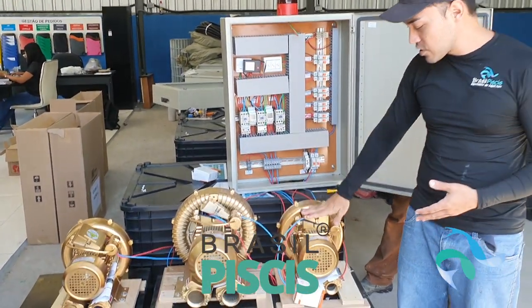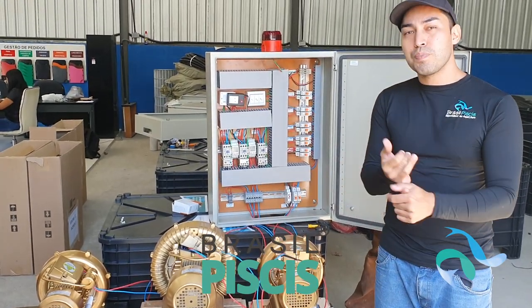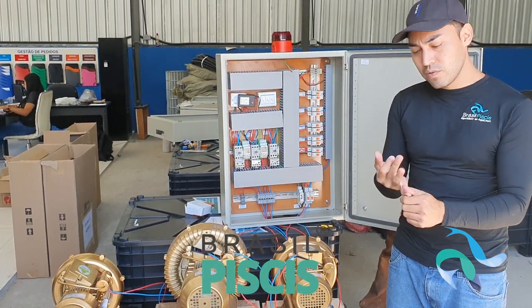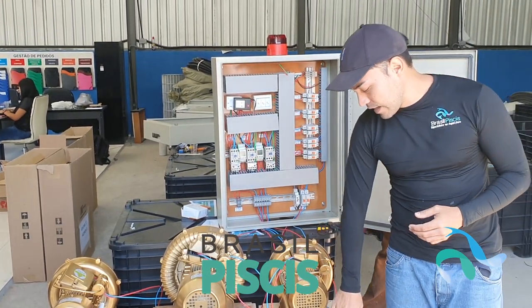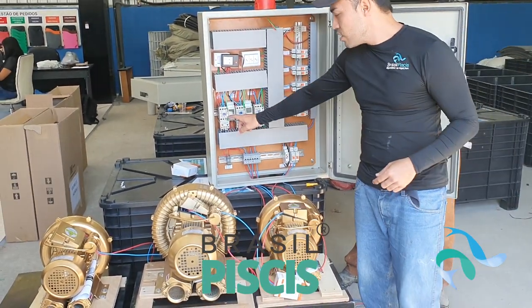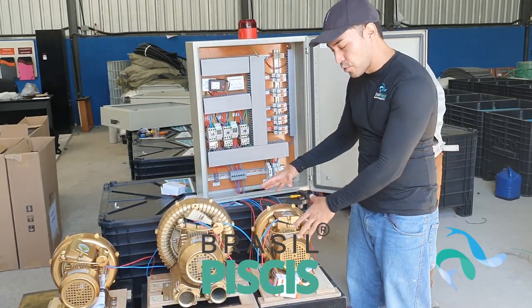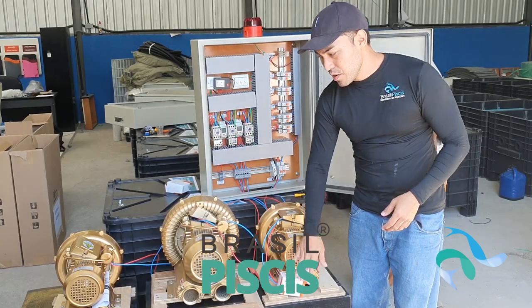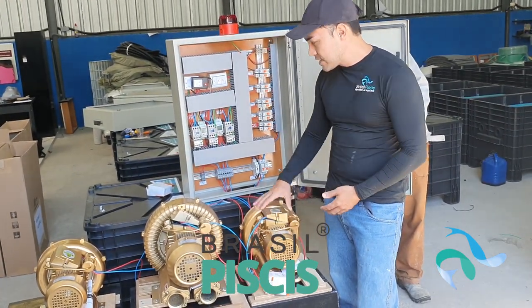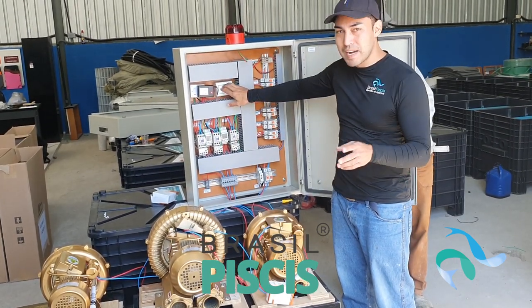Resumindo o vídeo de hoje: com a proteção térmica você protege o seu motor contra entupimento, travamento do motor — se o motor travar ele vai sobreaquecer e desarmar — problemas físicos e mecânicos no motor, entupimento de saída, má instalação hidráulica tanto de água quanto de ar. Você protege contra má instalação, travamento mecânico, entupimento, eletricista que liga errado — o motor ou vai entrar em curto ou vai sobreaquecer e desarmar. Também protege contra funcionário dormindo e queda de energia.